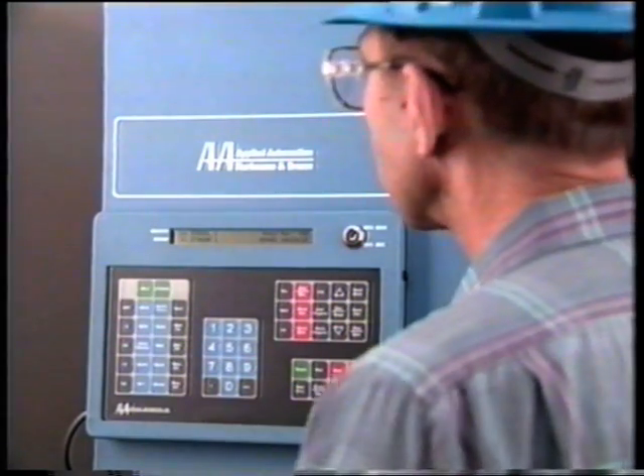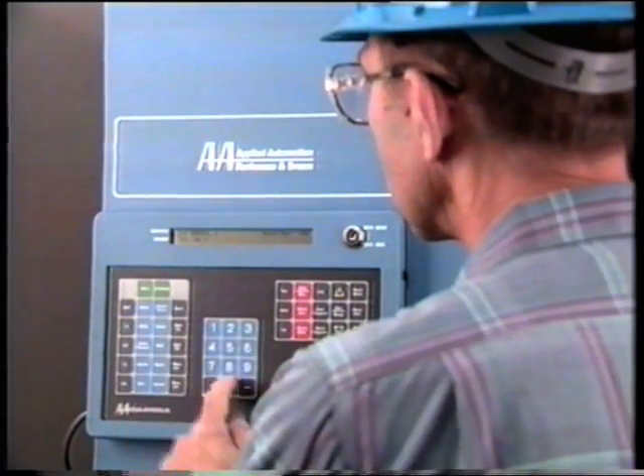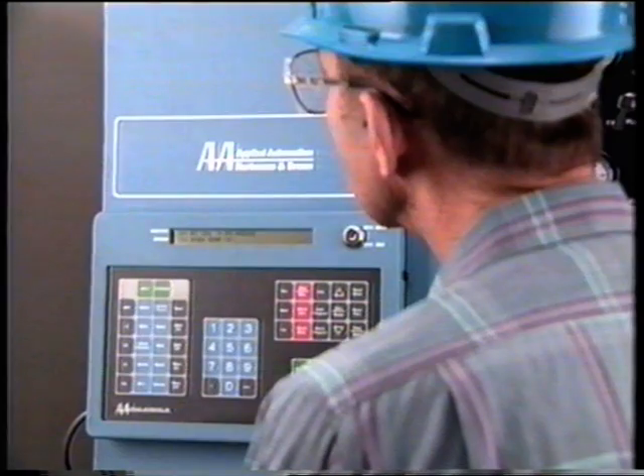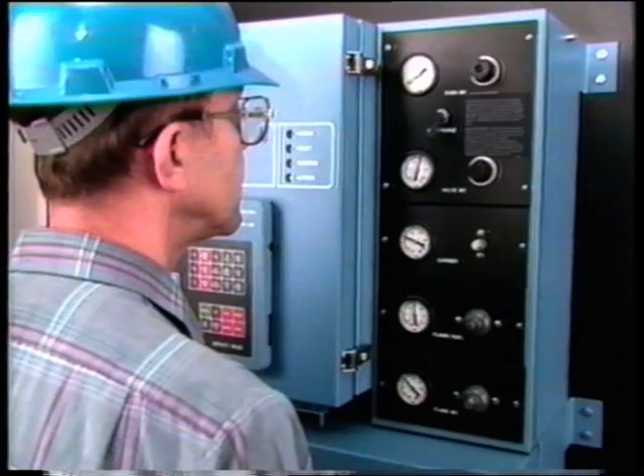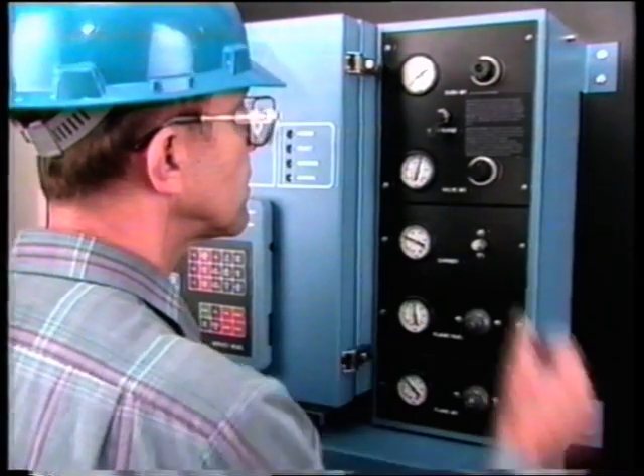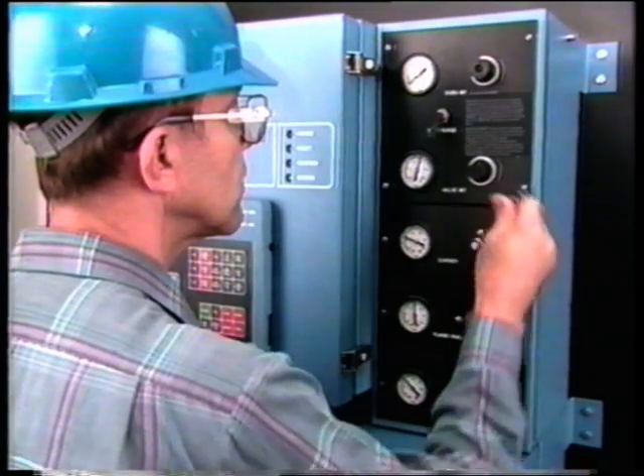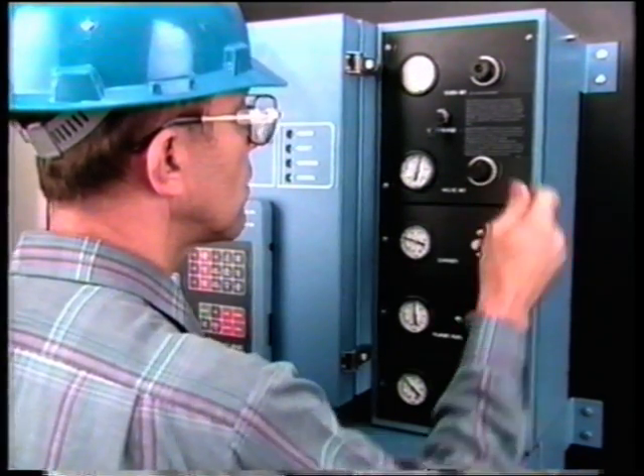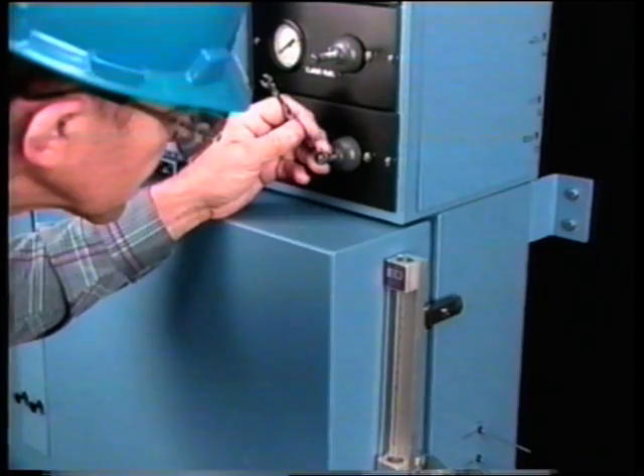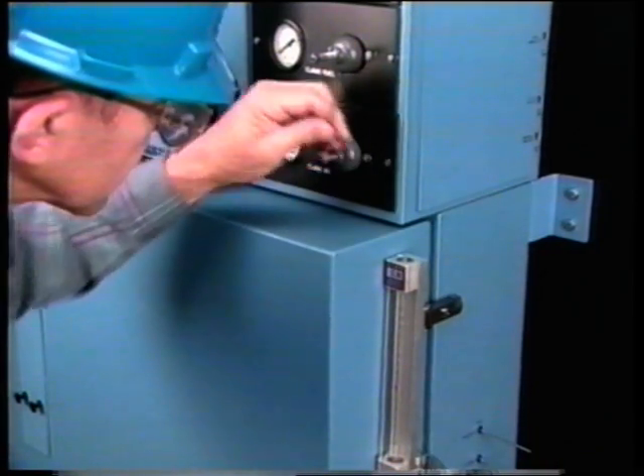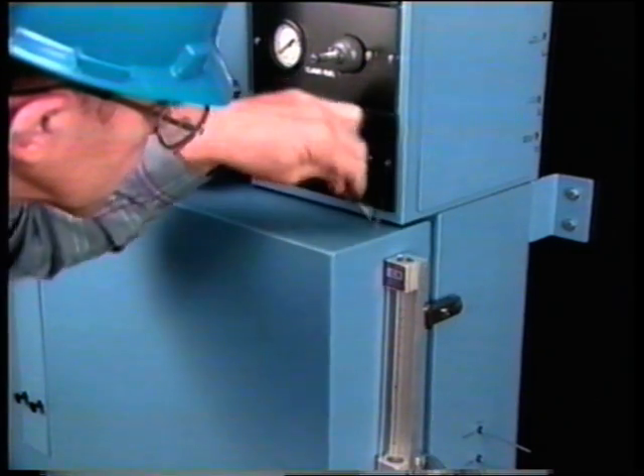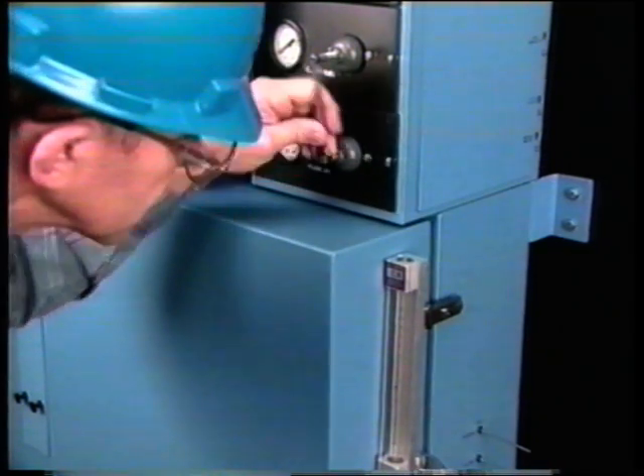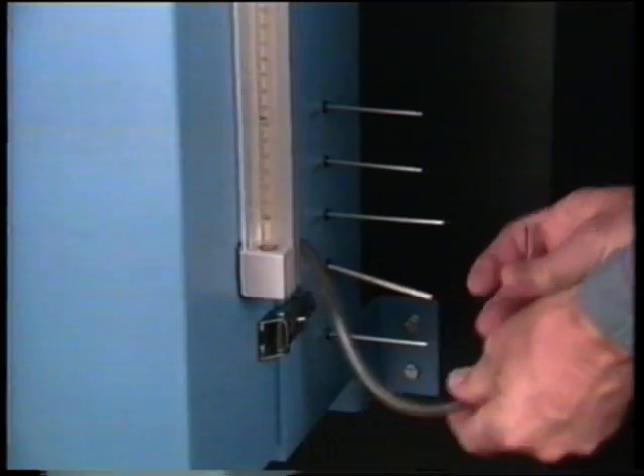While adjusting the detector flow, the analyzer and the air treater, if used, should be at operational temperature. Turn off the carrier gas, the hydrogen, and the flame air, and wait until they drop to 0. Connect the flow meter to the detector vent. Adjust the hydrogen flow to 28 cc's per minute. You'll skip this step if your system uses hydrogen as a carrier gas.